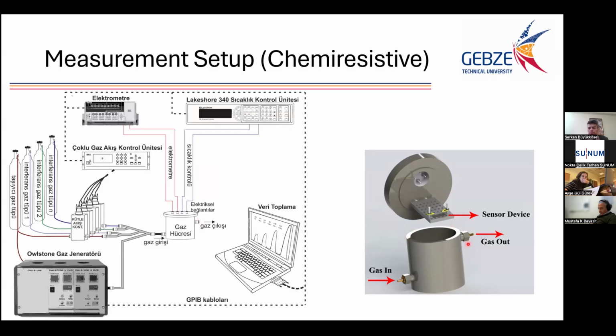It has approximately 1 liter volume, and low concentration gases are generated by a special tool. This is the gas generator here, and it's sent to the sample with carrying gases. Mostly in our case, it's dry air. All the flows are controlled by the flow controllers, and by using feed-through connections to the chamber, we get the sensor signals by means of the electrometer, and we can also control the temperature in case we don't have a self-heating structure on the sensors.